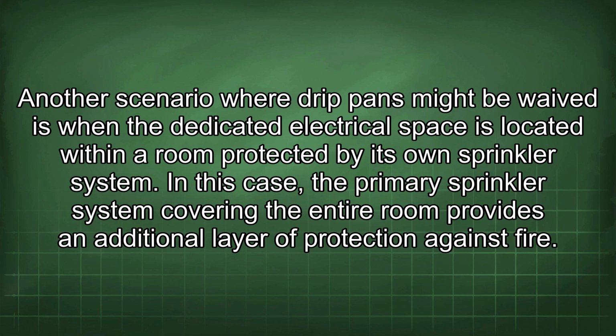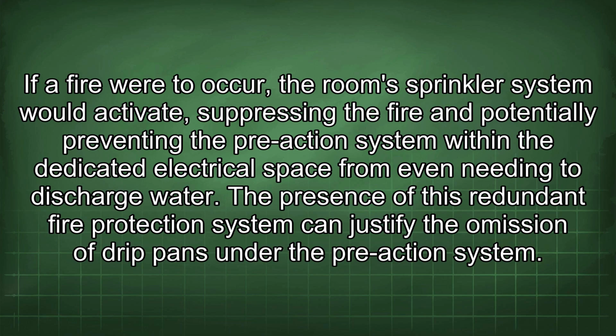Another scenario where drip pans might be waived is when a dedicated electrical space is located within a room protected by its own sprinkler system. In this case, the primary sprinkler system covering the entire room provides an additional layer of protection against fire. If a fire were to occur, the room sprinkler system would activate, suppressing the fire and potentially preventing the pre-action system within the dedicated electrical space from even needing to discharge water. The presence of this redundant fire protection system can justify the omission of drip pans under the pre-action system.